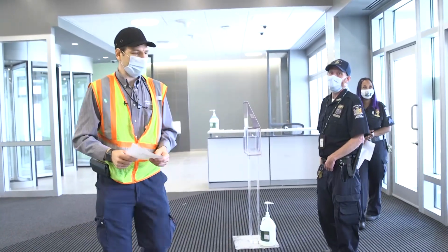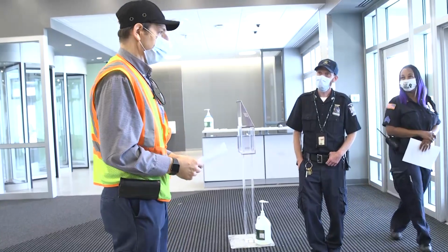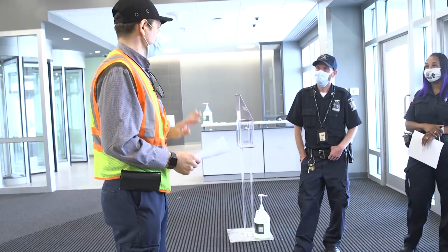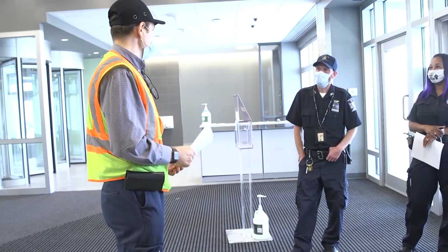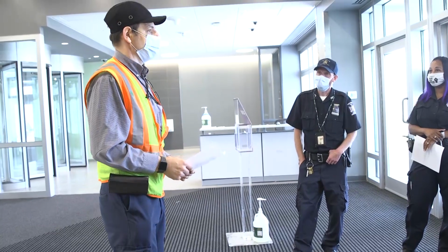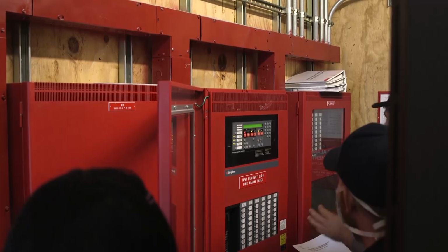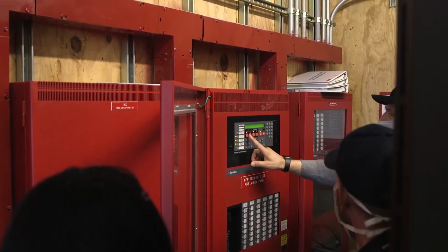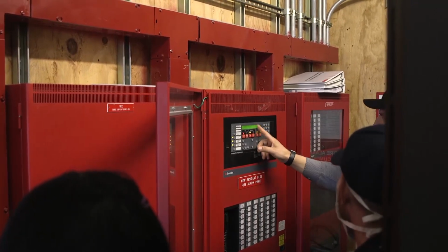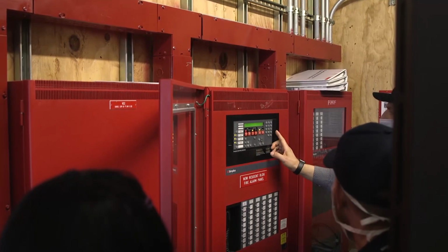Only duct detectors are supervisory, so you're not gonna hear from the duct detectors. Just from smoke detectors, pull stations and water flows, you're gonna hear this announcement. So you stop the noise and speakers right away. You can check. Okay, pull station is normal.